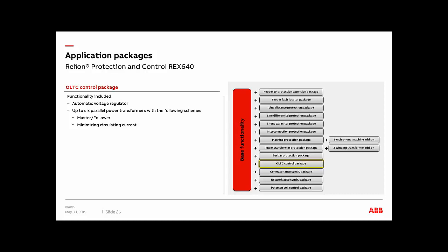And there's a 3rd one here, which is called the negative reactance principle. Similar to the minimizing circulating current, transformers do not have to be the same as far as impedance and number of taps, and this one does not require communications. So it's a little bit less ideal, since you don't have information on the other tap. It's purely based on current measurement. But that's an option as well if you don't have communication. And this is for your on-load tap changer control package.